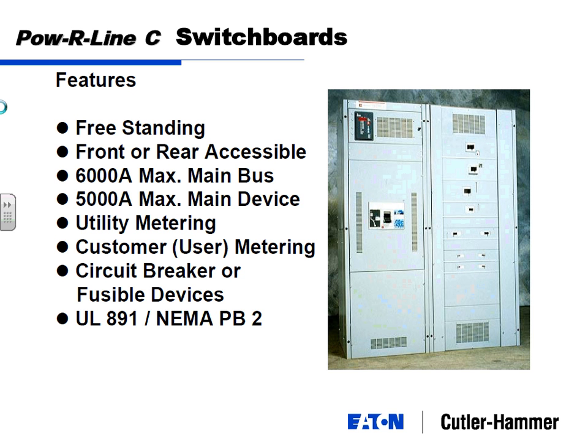So I mentioned they're freestanding, they sit on the floor. They can be front or rear accessible. Most commonly, people try and mount them against the wall, again, if you're saving footprint, because you don't need any rear access. But on certain devices or certain layouts, you want to put it in the middle of the room. It allows you to get around to the back, helps with your cabling or what have you. So it's got the 6,000 amp main bus. Right now, 5,000 amp is the maximum main device, main breaker, etc. Has capabilities for utility metering, customer metering, circuit breakers, fuses, and actually UL 891 is the standard for switchboards.